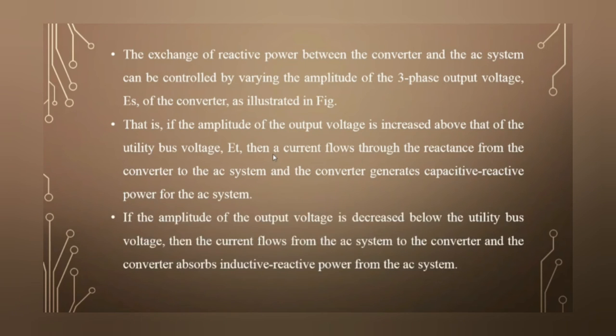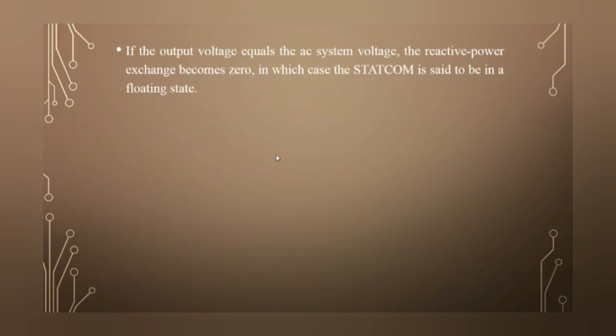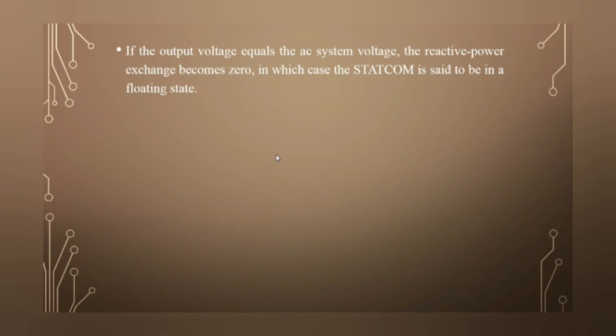If the amplitude of the output voltage is decreased below the utility bus voltage, then the current flows from the AC system to the converter and the converter absorbs inductive power from the AC system. If the output voltage equals the AC system voltage, the reactive power exchange becomes zero, in which case the StatCom is said to be in a floating state — when ET equals ES, there is no supplying or absorbing of reactive power.